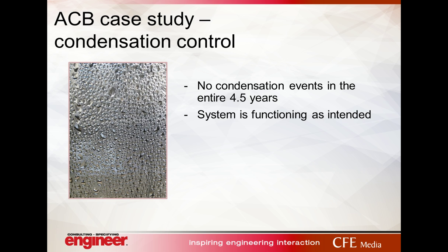Condensation is another big concern, but it's not like the coil. The coil in the chilled beam is a cooling coil. It's not a condensing cooling coil. It's not designed for that. We're not sending 42-degree water to it.